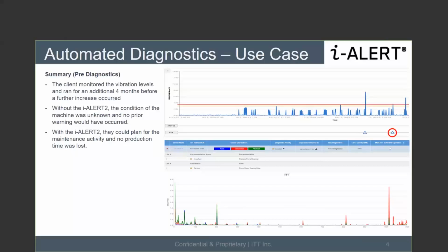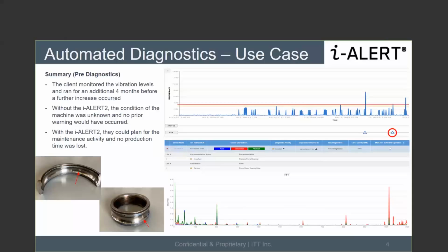So what they did is that they saw that this was a good reason to honestly stop the equipment and break it down. And one thing that they found out was, yes, it was a bearing issue. They did have higher vibration, higher temperature, and all that was correlated to a bearing failure. So the best part about this is that you were able to save the customer a lot of time, save the customer before a catastrophic event took place, and give them an idea of what to look at. And that was so valuable for the customer.